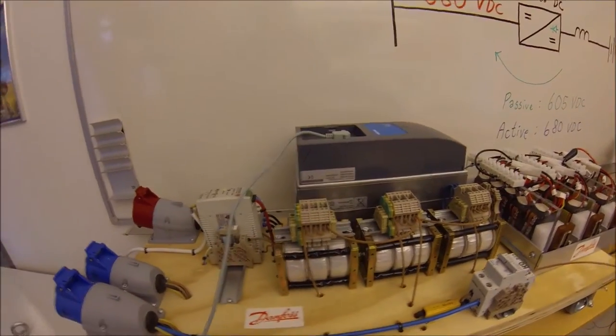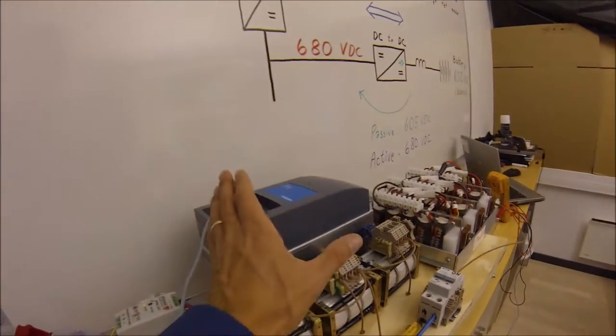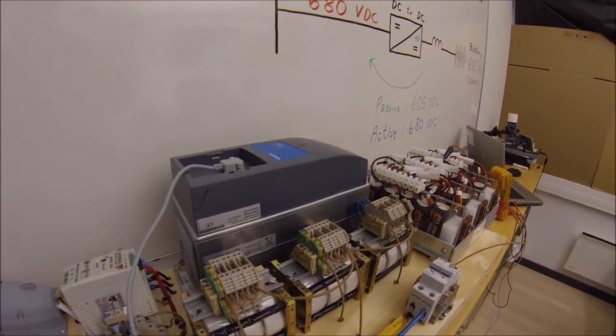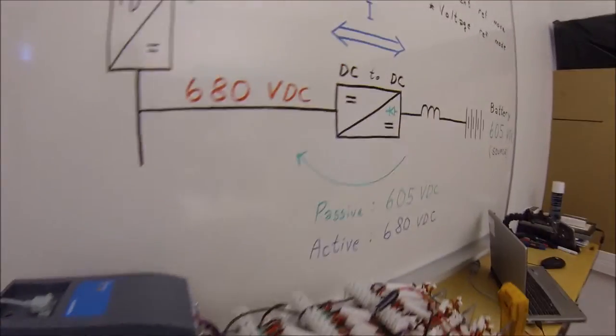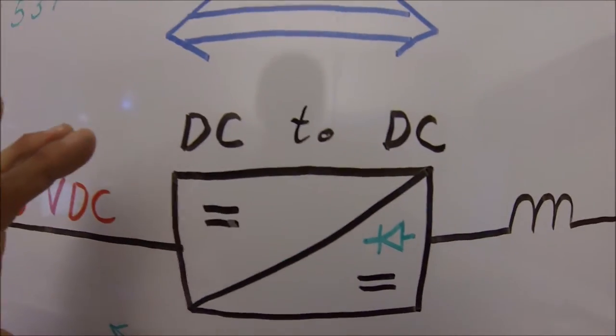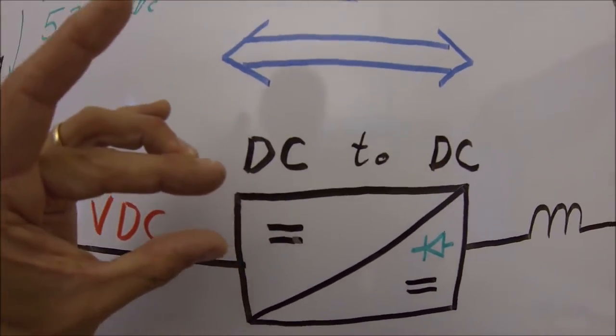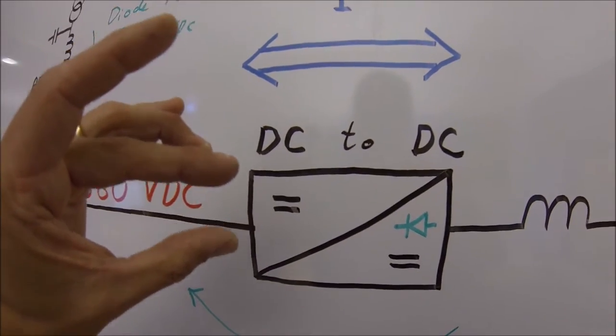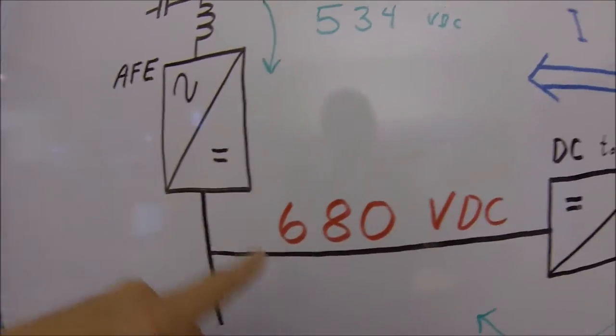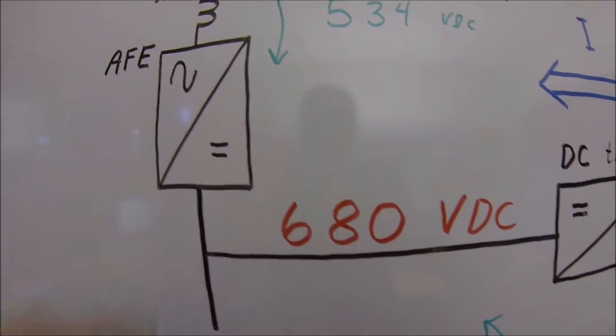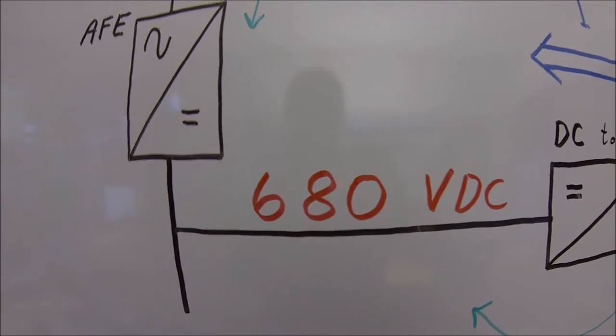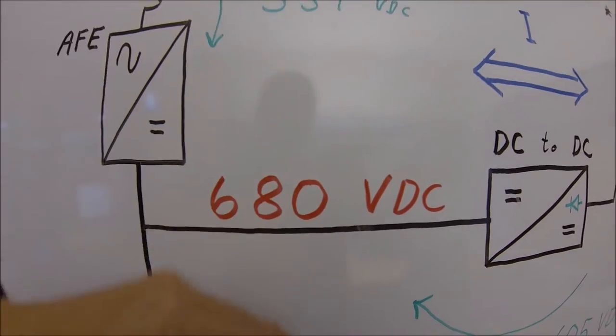We can also produce 680 volts from this place. And then we will use the over voltage and under voltage controller in the DC to DC converter to make a narrow window for the DC voltage to match the active front end. Load sharing is done with load drooping. We are doing a load drooping of about three percent.